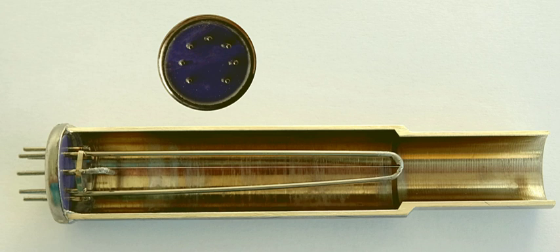Topic: Structure. The Pirani gauge consists of a metal sensor wire, usually gold-plated tungsten or platinum, suspended in a tube which is connected to the system whose vacuum is to be measured. The connection is usually made either by a ground glass joint or a flanged metal connector, sealed with an O-ring. The sensor wire is connected to an electrical circuit from which, after calibration, a pressure reading may be taken.